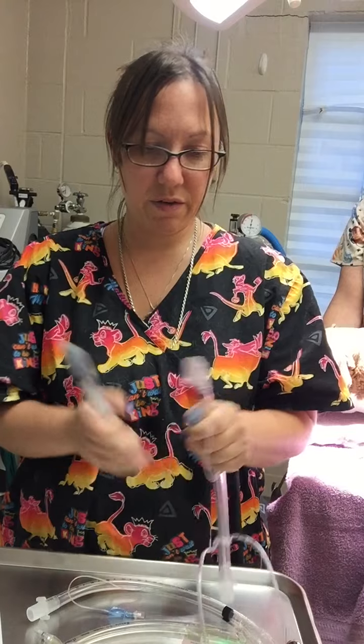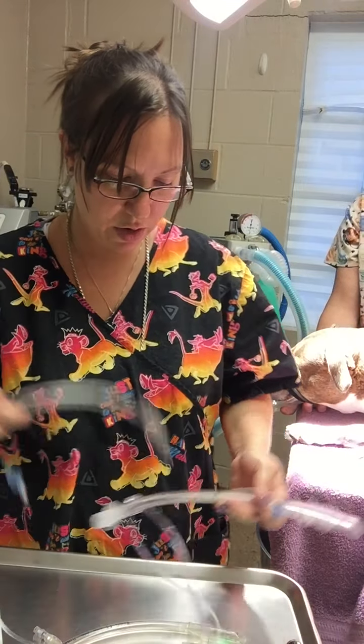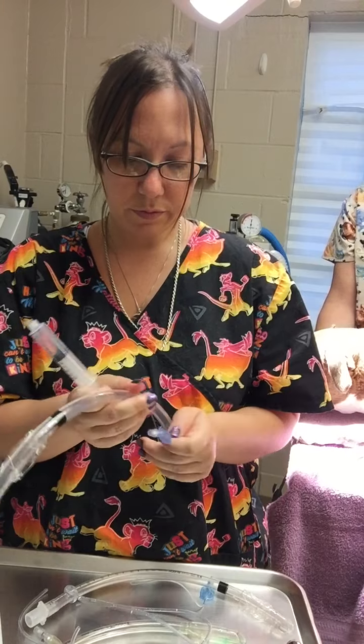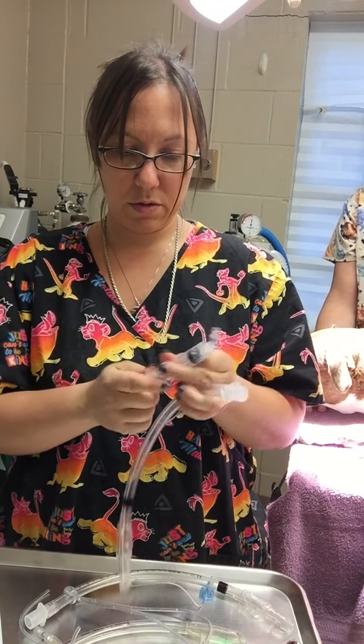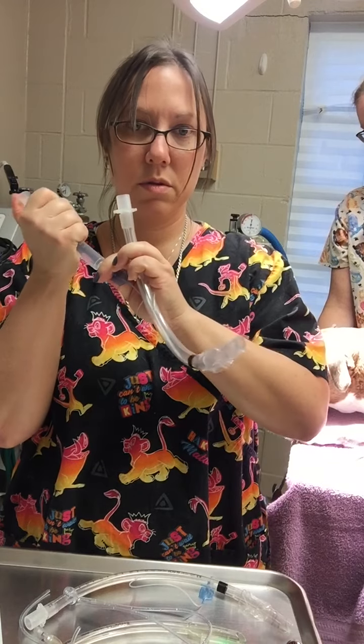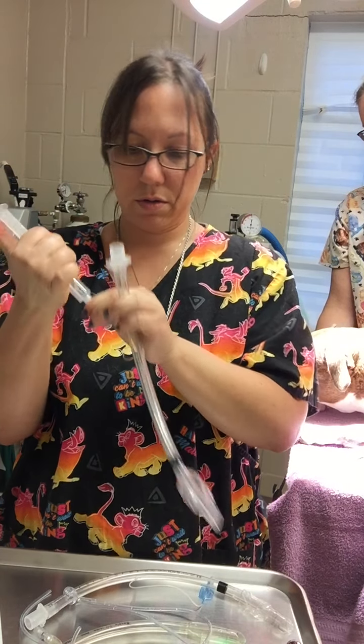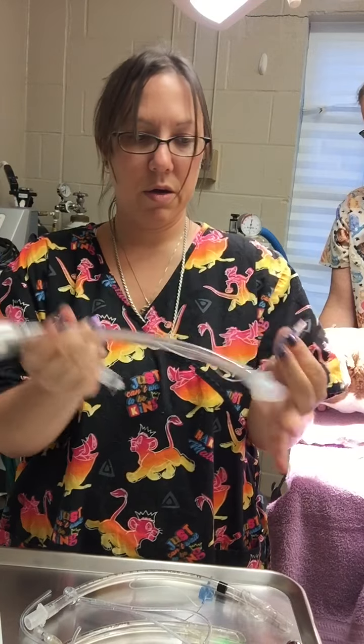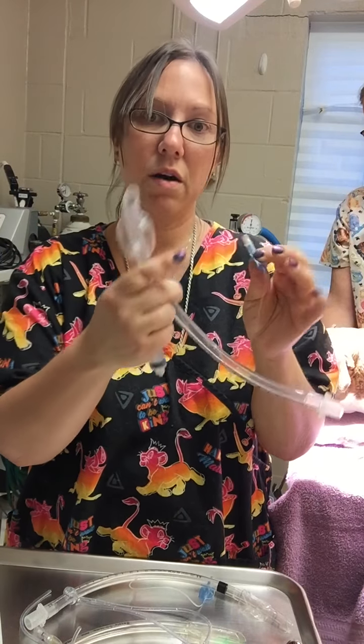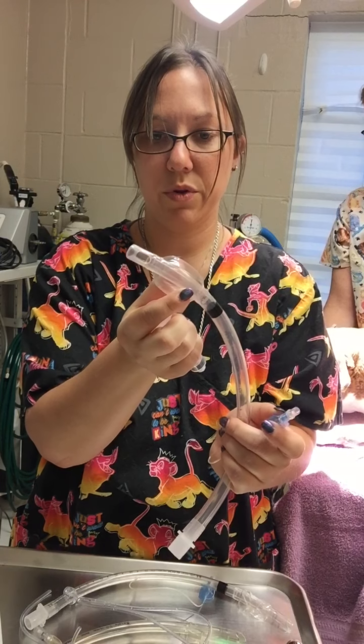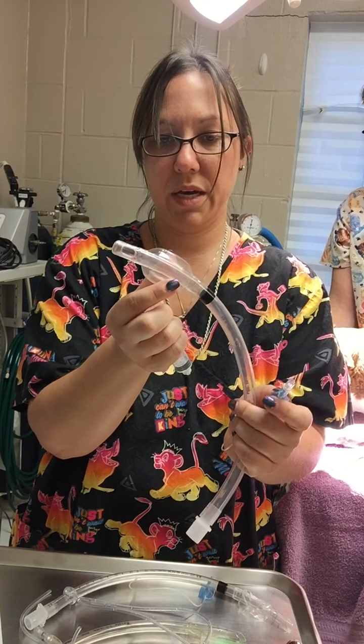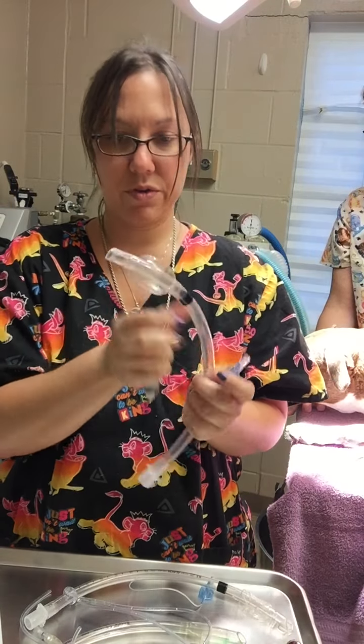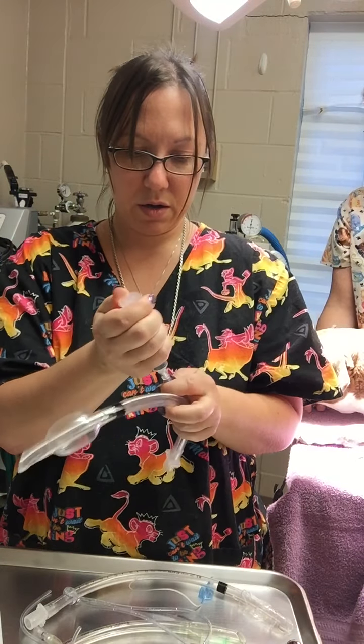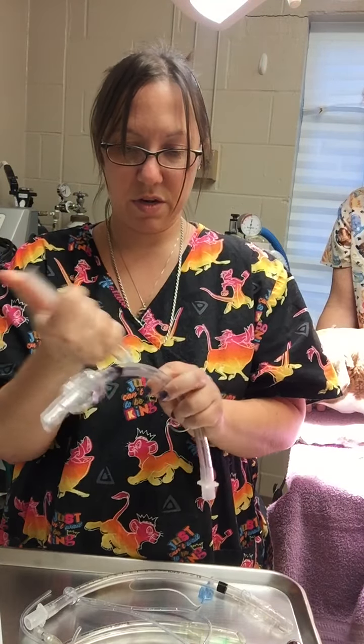And so now I'm deflating the cuff to ensure that it's going to go smoothly down, and I'm going to check the 10 tube as well. Okay, so I'm pressing pressure on the cuff, visualizing and also feeling the balloon. So its pressure is maintaining. I can feel that give back and forth. So there's no leak, there's no gunk. So the number 10 is good, just in case that 9.5 is too small.